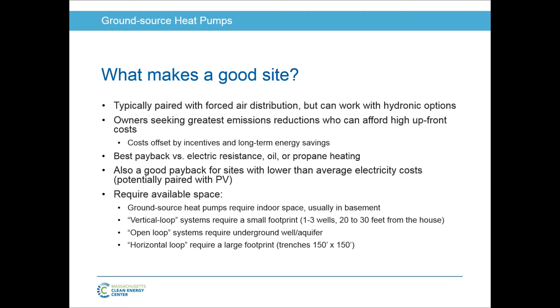In terms of the outdoor space, we've talked about this a bit, but for the indoor you will need somewhere for your indoor heat pump, typically a basement, the same way you'd need for your furnace. For a vertical loop system, like we saw at the beginning, you need a smaller footprint, maybe 1 to 3 wells, something that could potentially fit under a driveway. An open loop system requires access to an underground well or aquifer on your property. And the horizontal loop involves less drilling but does require a pretty large outdoor area, say typically 150 by 150 feet.